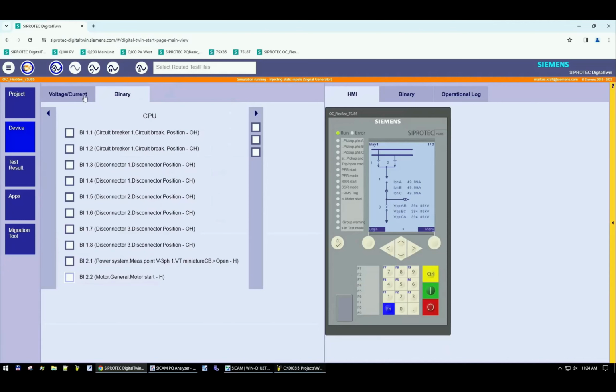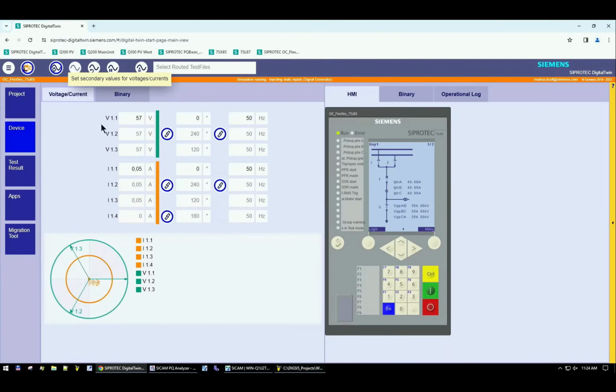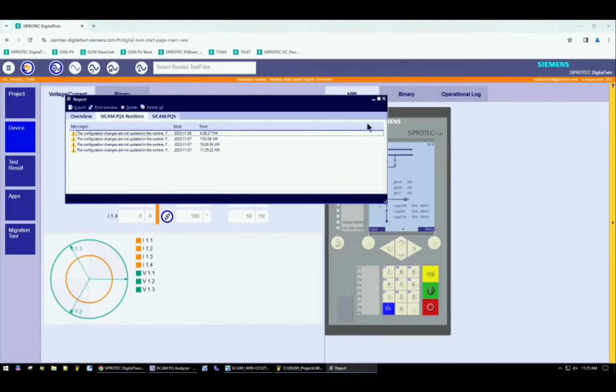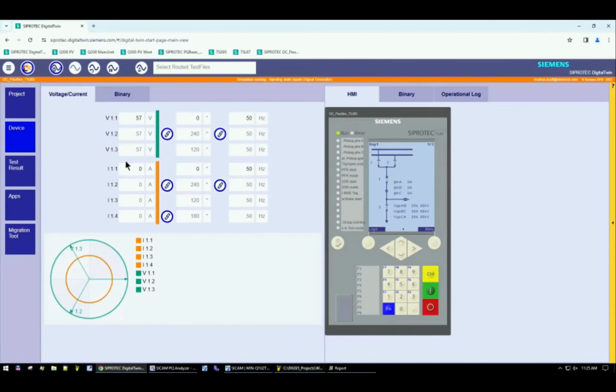One more test scenario is the current trigger. When it goes above 0.9 amps, it should show us this IRMS trigger LED. And also via trigger routing, we are starting the SSR. For that, I will now increase the value: 15, 25, 35, 45, 55, 85, 95. And now the trigger takes place, current RMS, slow scan started. Very good. The trigger is gone. The slow scan takes these 6 seconds post-trigger time after the signal went down.